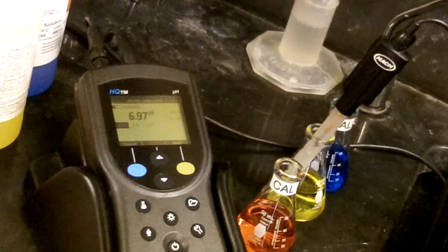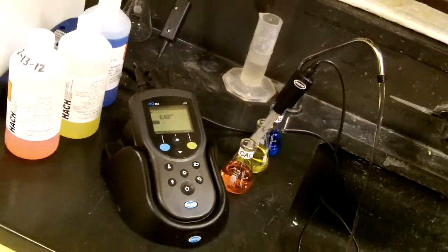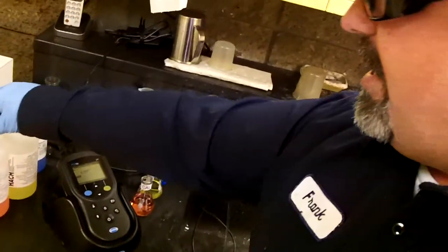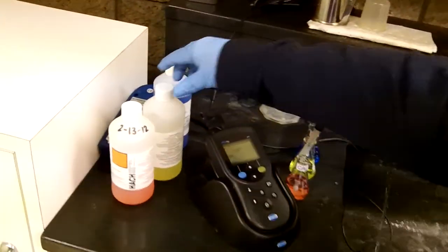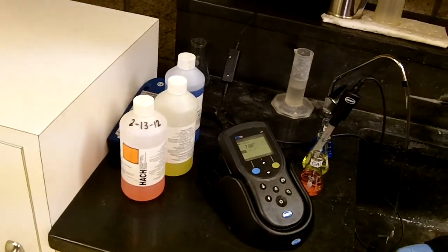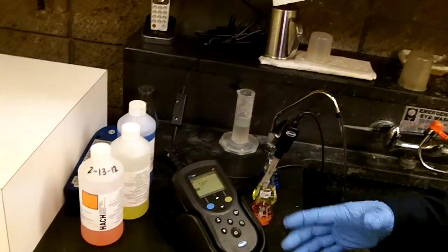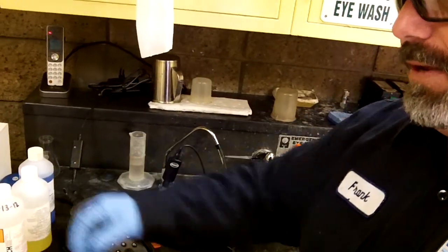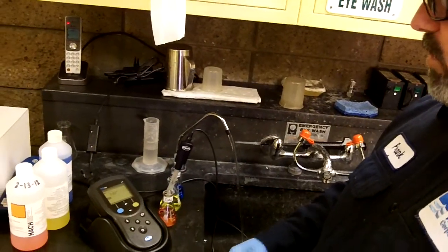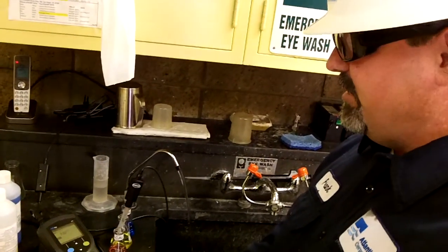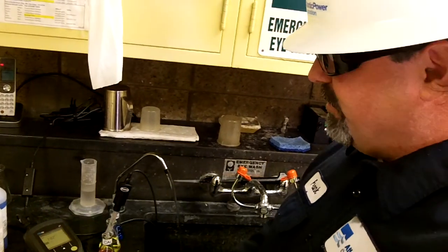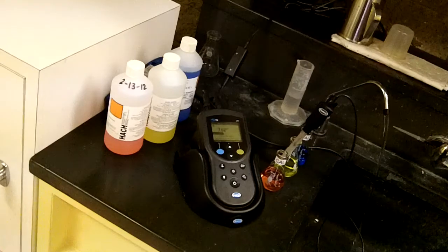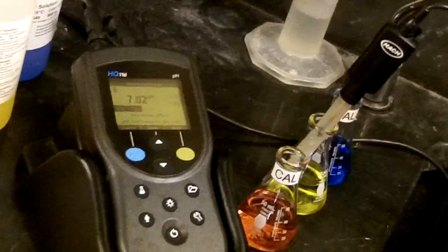So it's important that you use the fresh buffers. It's also important to realize how old your buffers are, because these will dissipate over time. And if the buffers get too old, if they've been sitting for too long after they've been opened, then you won't get an accurate calibration. So just take note of how old your buffers are. Okay, so this came out at 7.02, which is fine. That's well within range, and that looks good.